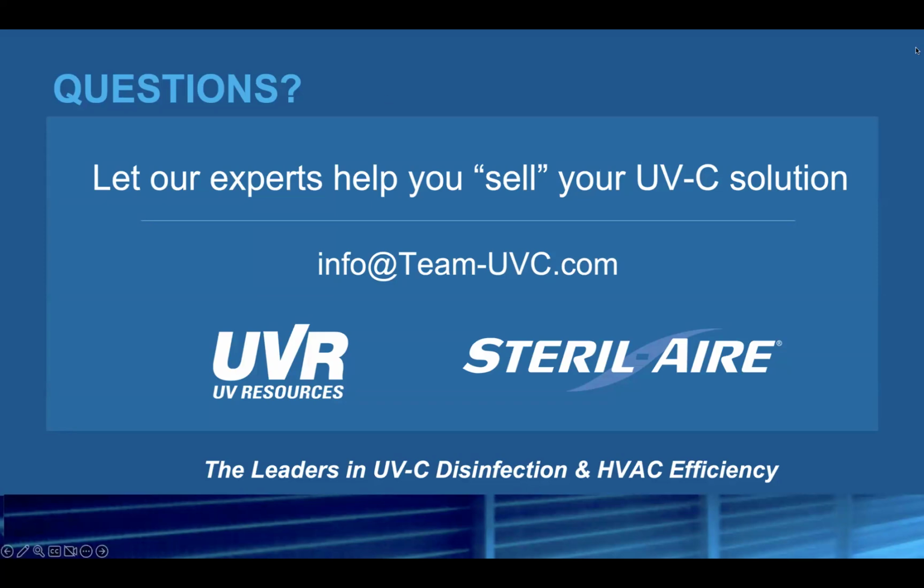We have one more question. How much room do you need to install the UVC? Can they be retrofitted on like a rooftop unit, or do we need a larger or custom buildup? No, great question. Typically, we like to be about 12 inches away from the surface of the cooling coil on the downstream side. And some smaller rooftop units really don't afford that amount of spacing. So the workaround is, in some cases, you might have to have two lamps because they're mounted closer to the coil, and you don't have that area for the energy to reflect and bounce around. But there really aren't too many air handlers, even down to small 5-ton rooftop units, that can't or won't accommodate at least one UV lamp.